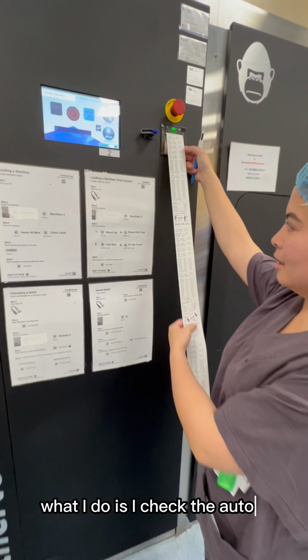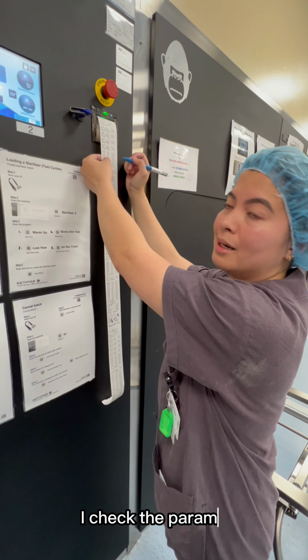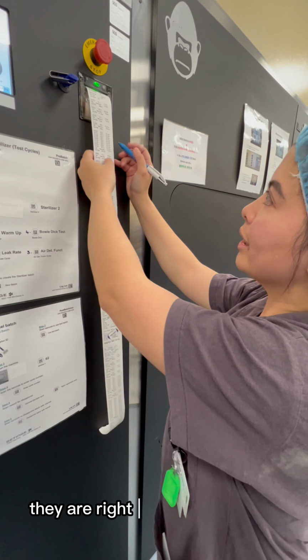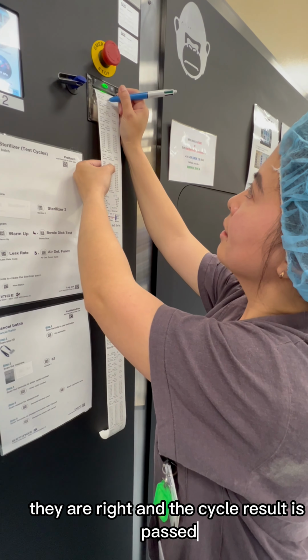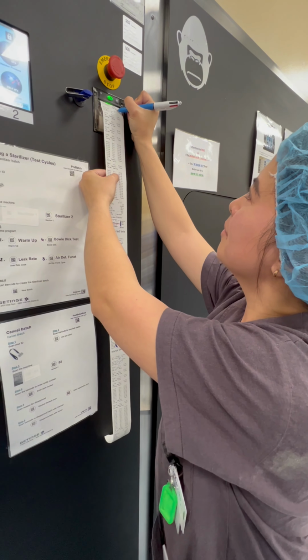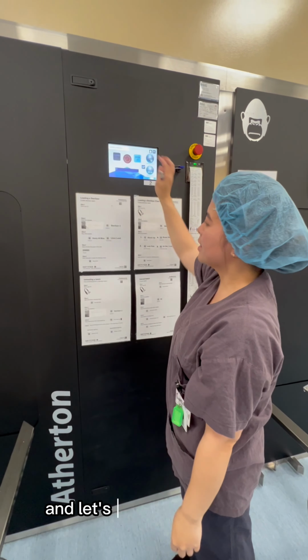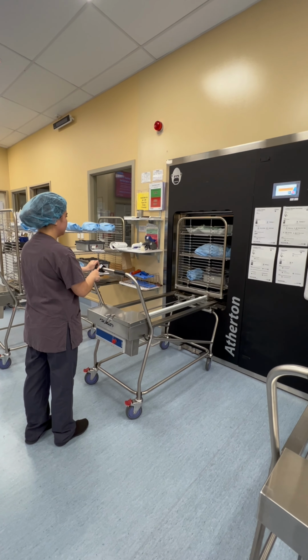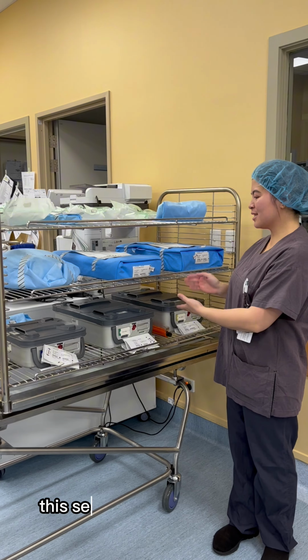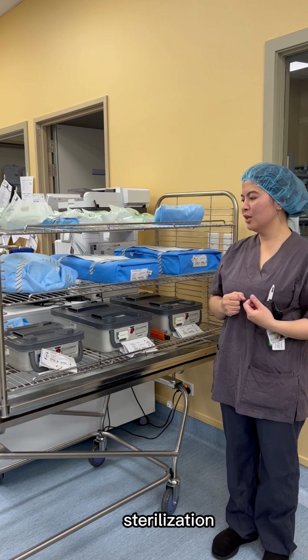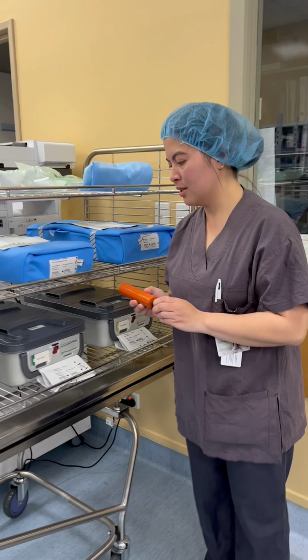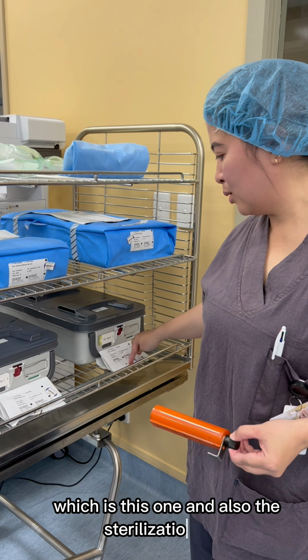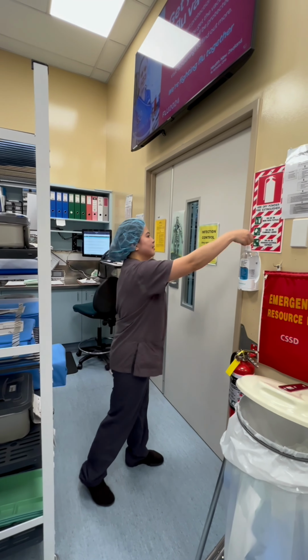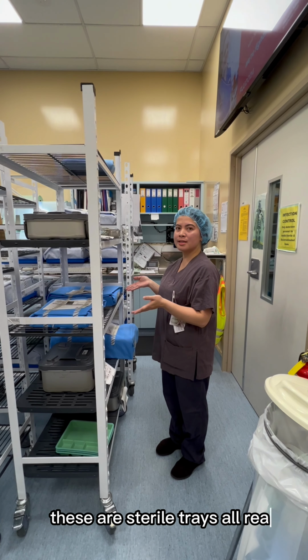What I do is I check the autoclave printout. I check if the parameters are right, and if the cycle result is passed, and then my name. And let's open the autoclave for unloading. These sets of instruments had just gone under sterilization. I'm going to check the indicators, which is this one and also the sterilization tape. And it turns out black, which means they went through proper sterilization. So let's get inside of this. These are sterile trays already and they are completely full, and it's time for dispatching.